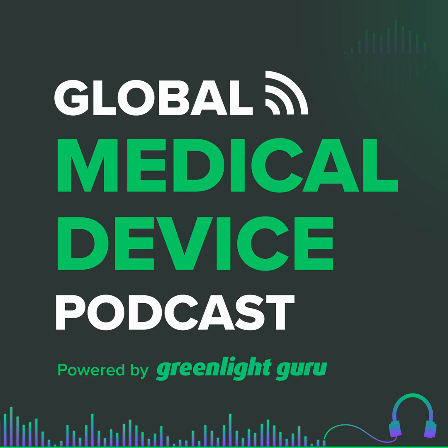Yeah, great question to start to close our discussion. And by the way, as I'm sure our audience appreciates, we're just scratching the surface on this concept. There are so many more things that we could talk about, but just a couple of final recommendations and words of advice. First of all, if you're considering a PCCP, in nearly all situations, I would bring that up in a pre-sub. That kind of goes without saying. Yeah, although it will make your pre-sub more complicated, because now you're talking about not just your current device, but your potentially modified device in the future.